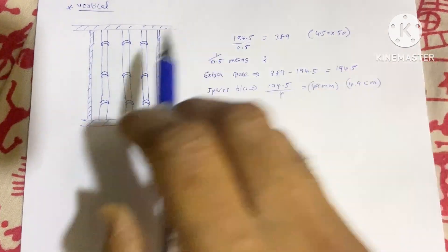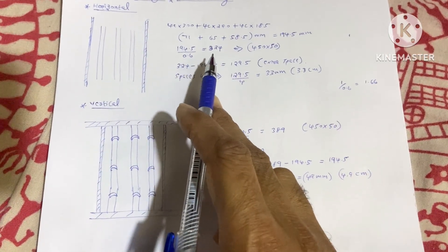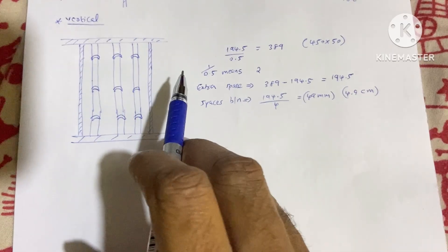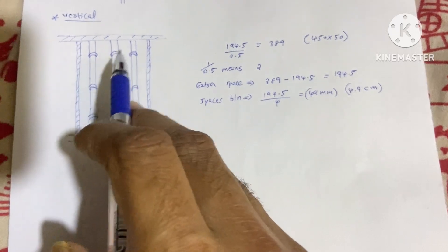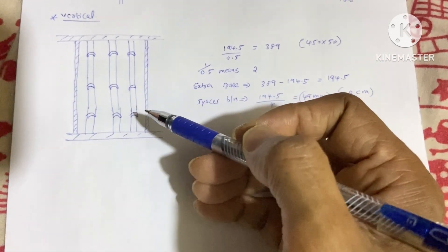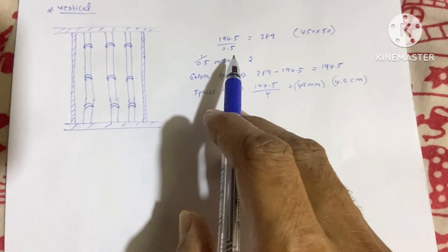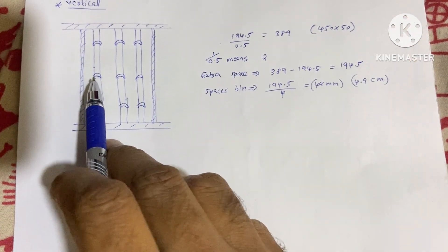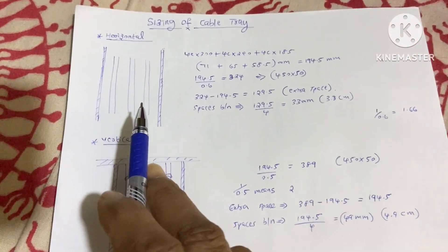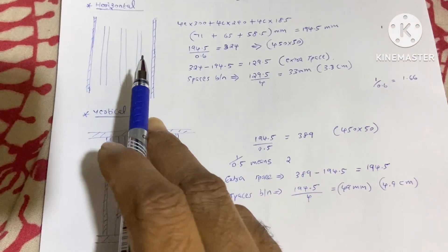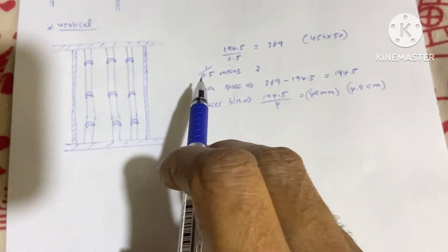You might be wondering why we use the 0.5 factor for vertical cable trays. For vertical cable laying, we are required to use cable cleats. When the cable tray passes through each floor, we need to install 3 cleats. On both sides of each cable, the cleat takes up 2.5cm of space. In the horizontal cable tray we used cable ties, but for vertical trays we need cable cleats — that is why we use the 0.5 factor, which provides extra space to accommodate them.